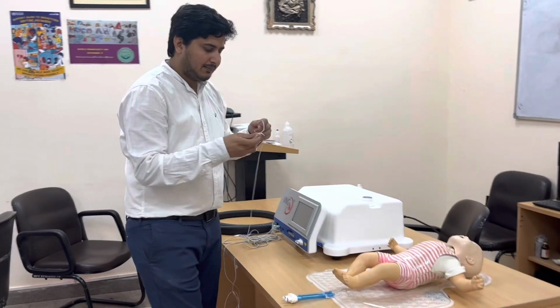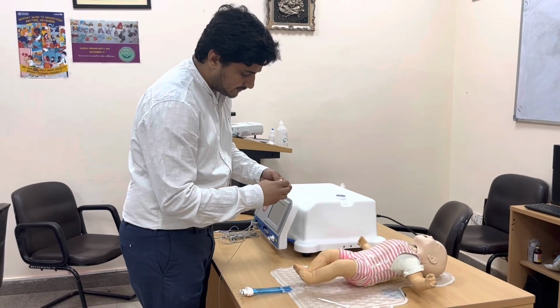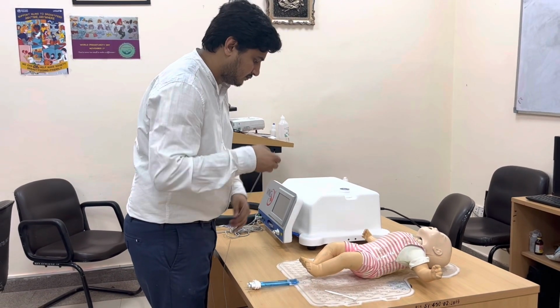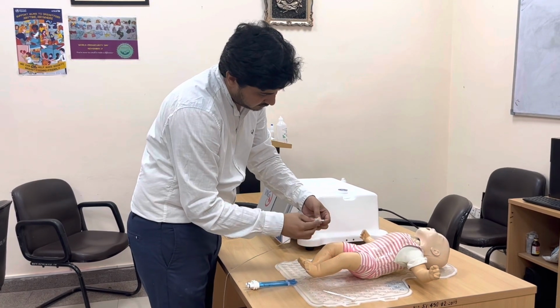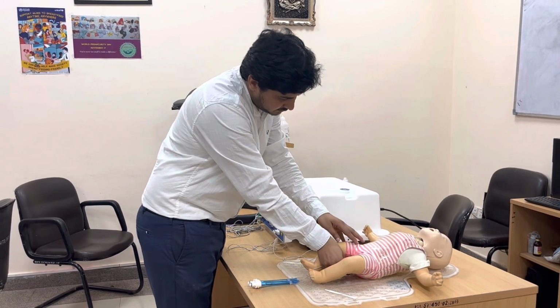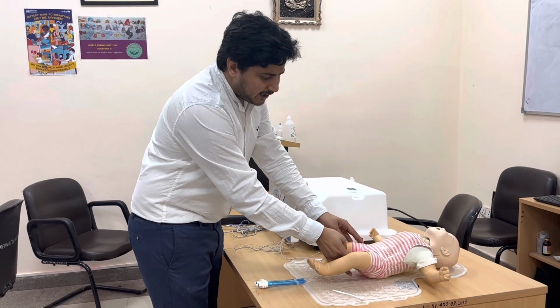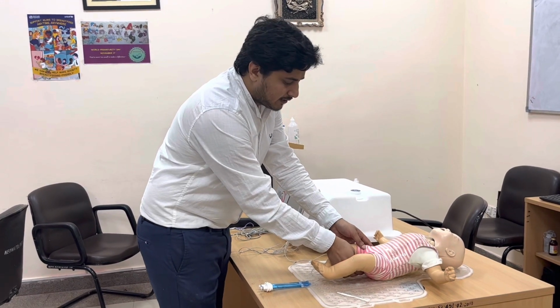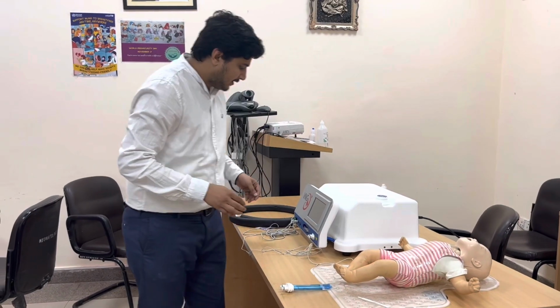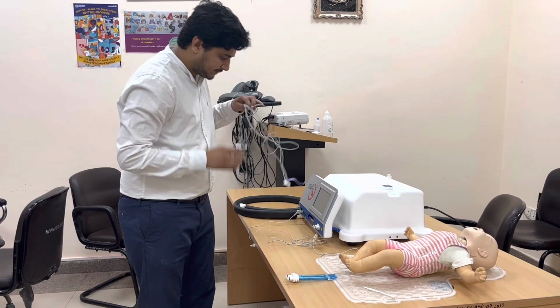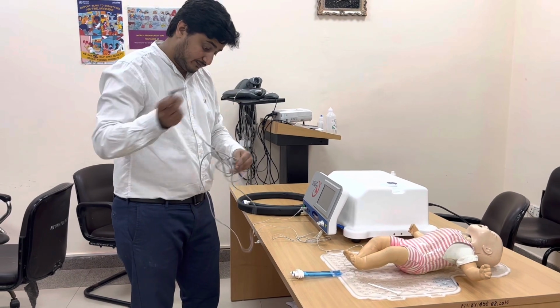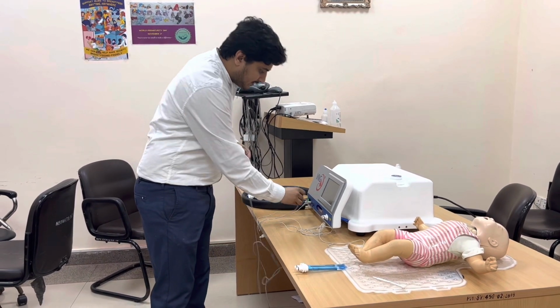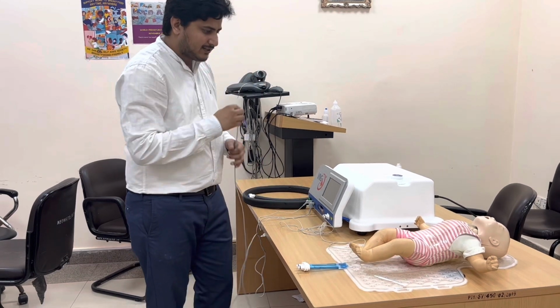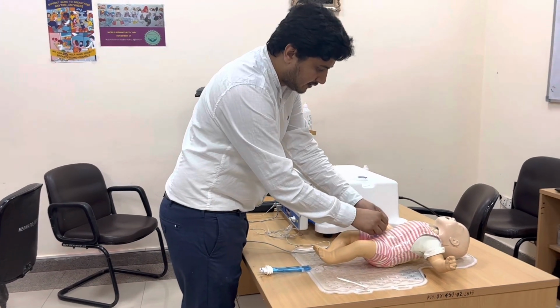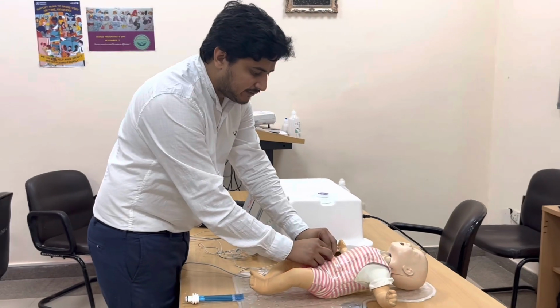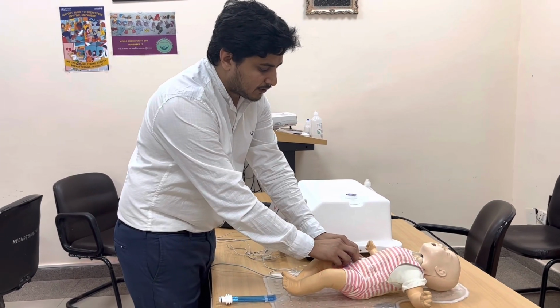First, I am attaching the rectal probe to the baby. The rectal temperature probe, which monitors the target core temperature, should be inserted at the level of 3 to 5 cm depth. Next, we should attach the skin temperature probe, which acts as a reference, in the right hypochondrium. The whole device takes feedback from the rectal temperature probe for the process of cooling.